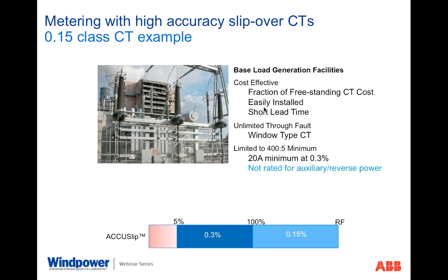So in front of this combustion turbine facility, you see 3 slipover CTs in a 0.15 class metering the power flow from that facility onto the transmission grid down in Texas. The advantage here is it's less expensive than a freestanding CT. It's easily installed. It doesn't have infrastructure requirements for a freestanding type device. But the advantage of the CT is we were able to get 0.15% performance, unlimited through fault, because it's just a passive slipover CT, a window type CT provided over a cable terminator or a bushing of a power transformer.